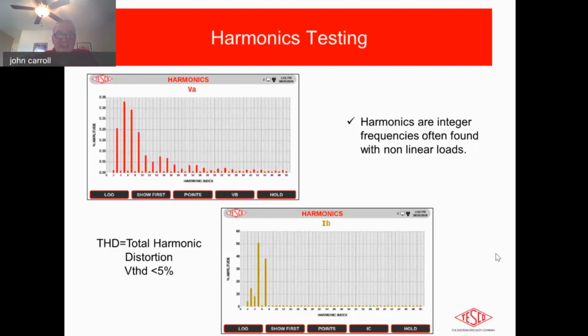But the essential thing to take away from this is, you can see here, there's just a couple of slides I put together, one of which is the harmonics on the voltage side. This is A phase on the top left there. And on the bottom, we've got harmonics on B, just as another example. But you can have it on A, of course, and it's the same phase. The important part about this is the amplitude on the left-hand side here, as you can see, is in percentage. That's percentage of the actual fundamental. We don't have the fundamental in here because otherwise it would have swamped this completely.